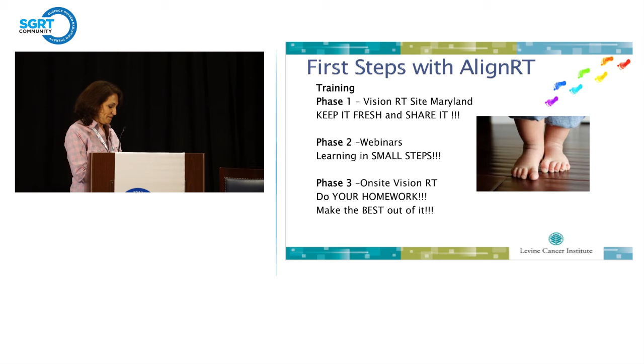Acceptance and commissioning. While we are not using the system, I went through the acceptance. Basically, hey, it's bought, go through it step by step. Hey, you bought this, it's working, and they are just selling you. Can you use it in your clinic? No, not yet. We have to do the commissioning and make sure that this add-on system is validated for your machine, for your other equipment and systems, from your CT to your treatment planning system to your treatment, and adding on the Align RT, they all need to be validated and talking to each other properly for all the possible clinical situations.